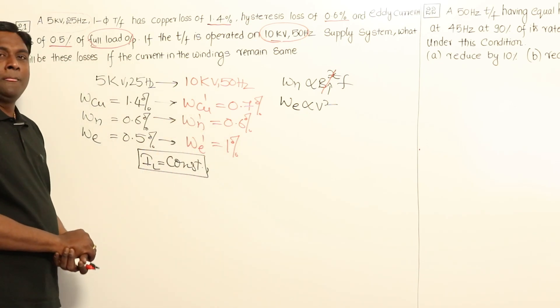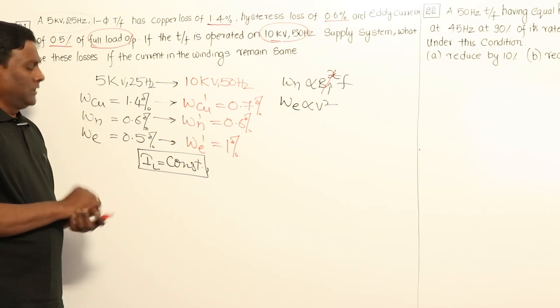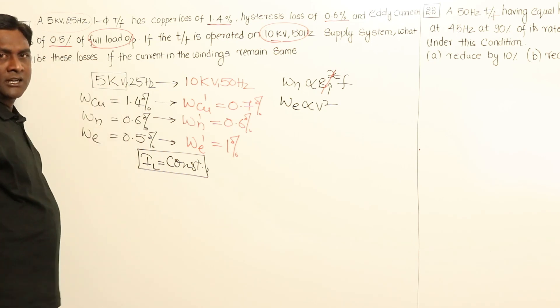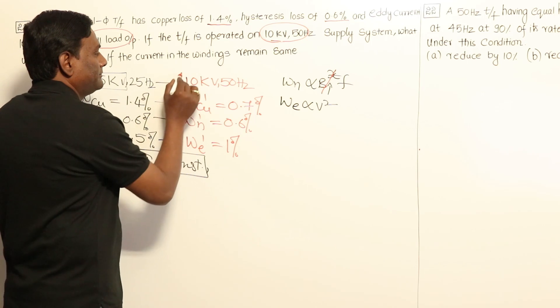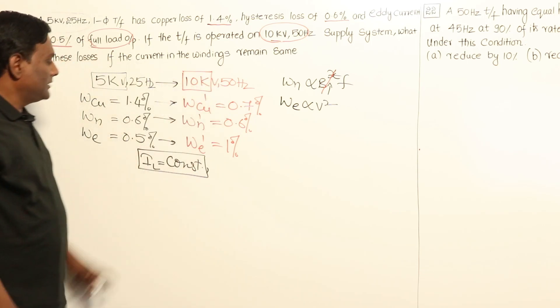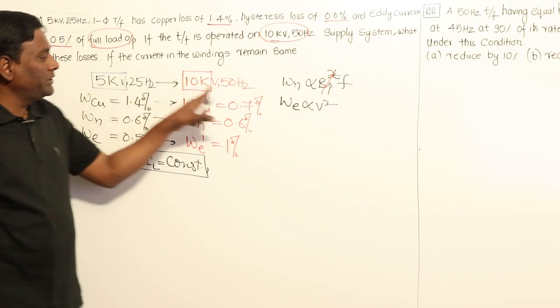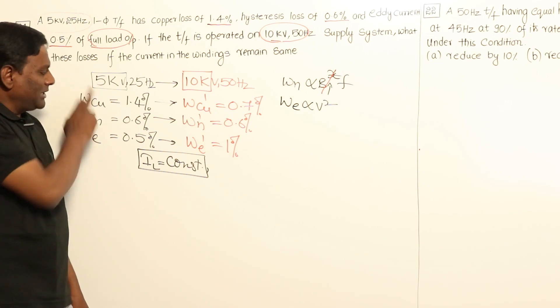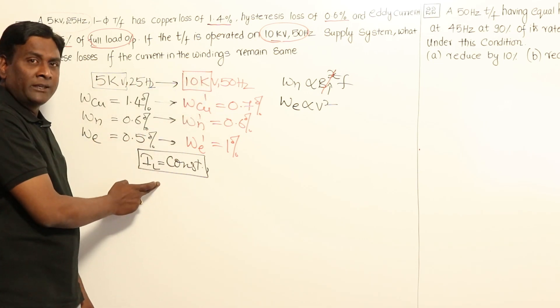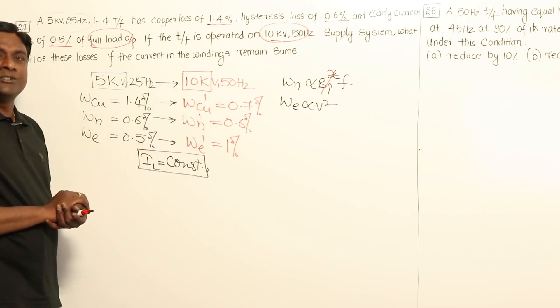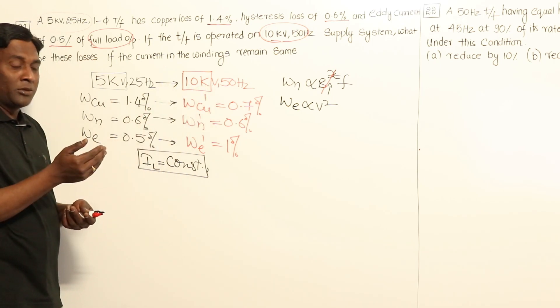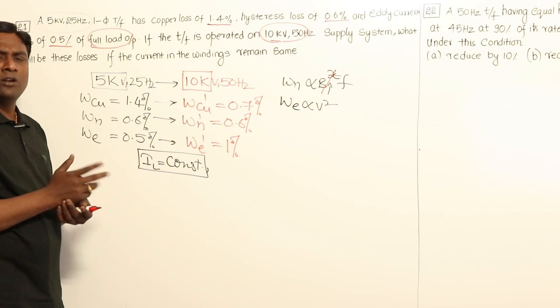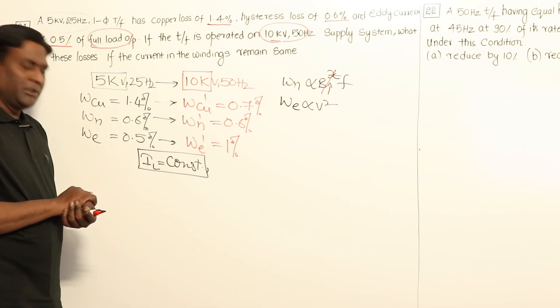Confused? Let's understand. At 5kV with line current constant and at 10kV with line current constant, the rated capacity is getting doubled — rated KVA equals voltage multiplied by current; voltage is doubled, current remains the same, so rated capacity is doubled. Though copper losses in watts are the same, the percentage of copper losses will be half.